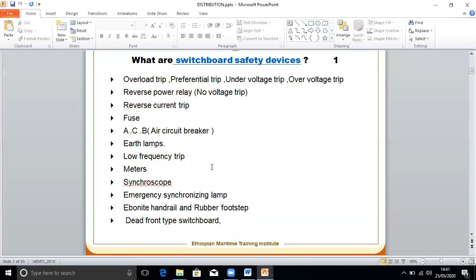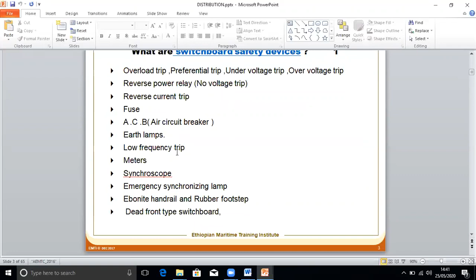Okay, so dead front type means the switchboard has no live parts on the front of the panel. Each framework is rigidly constructed of steel angles for vibration resistance, to which door type panels of 2.3 mm thick steel are hinged at one side, and the other side is latched for securing it. This is known as the dead front. Dead front means you cannot get anything live on the front side. It's all sealed. So these are the general safeties you need when you work on a switchboard. You must specify certified insulated gloves and a certified floor mat, a rubber mat. And these are the general safety devices which you find on the switchboard.